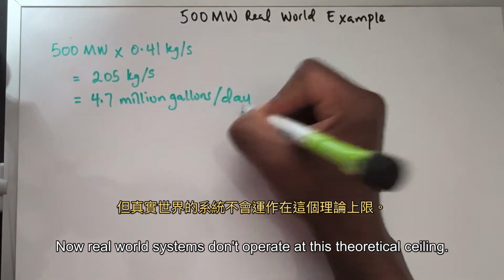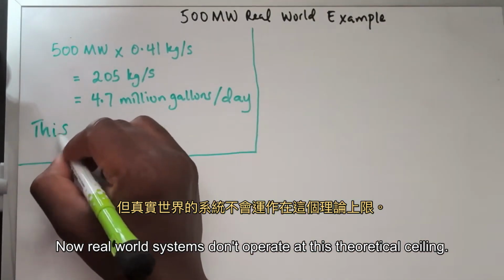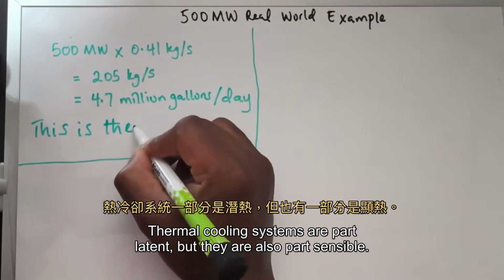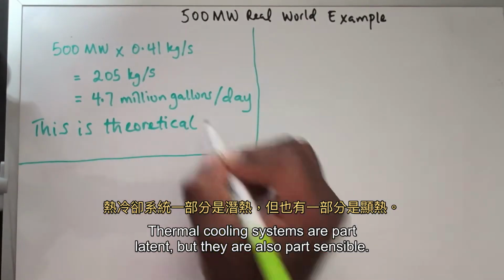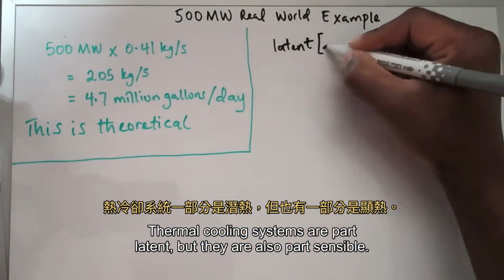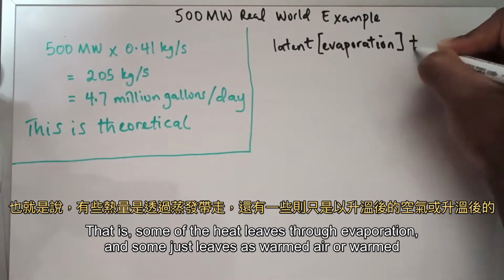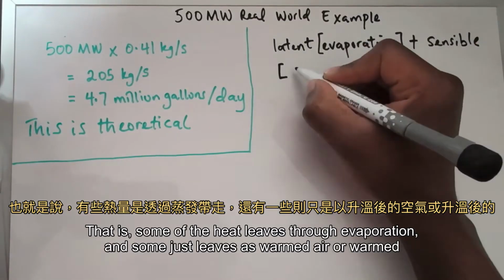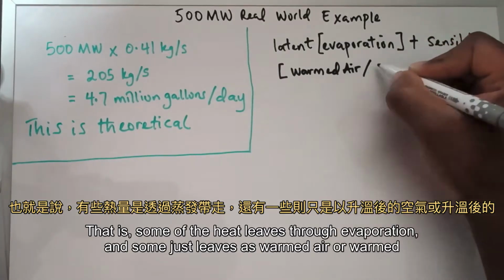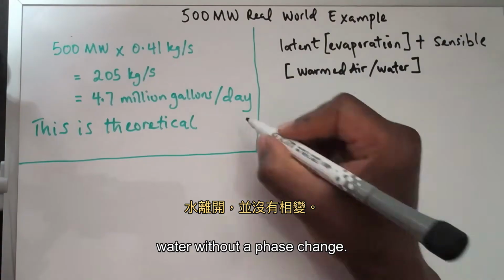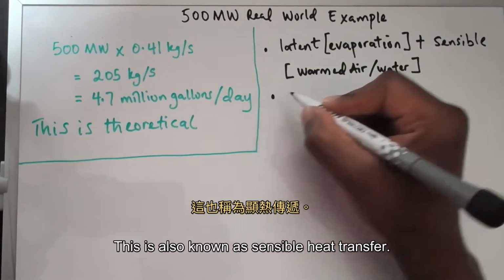Now, real-world systems don't operate at this theoretical ceiling. Actual cooling systems are part latent, but they're also part sensible. That is, some of the heat leaves through evaporation, and some just leaves as warmed air or warmed water without a phase change. This is also known as sensible heat transfer.